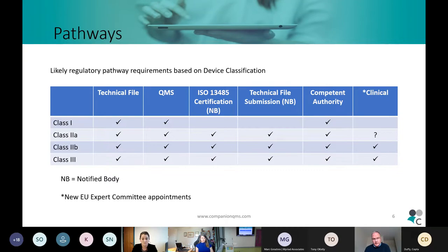You will be obliged to have an ISO 13485 certified system through a notified body of your choice, providing they're MDR designated and can provide that 13485 certification. You'll also be obliged to submit a technical file, which in a nutshell is a summary of what's happened in your design control process, to the notified body for their approval and concurrence with your recommendation that this device should be CE marked.